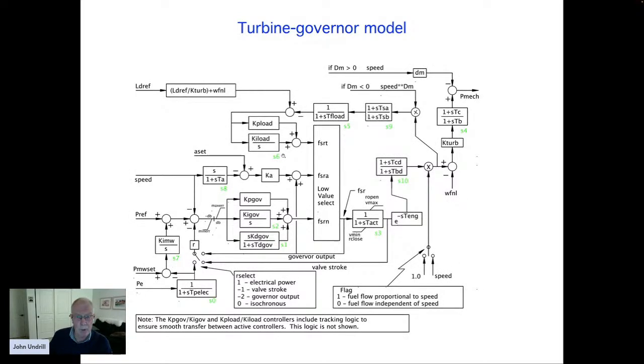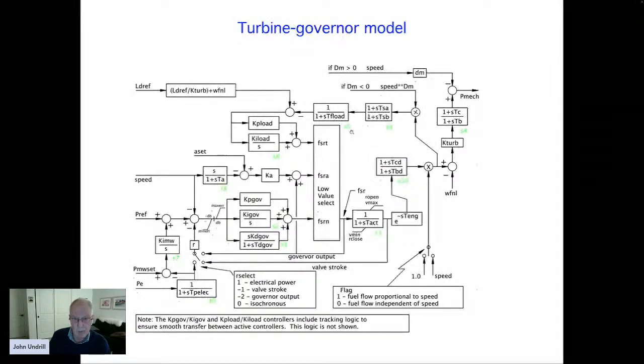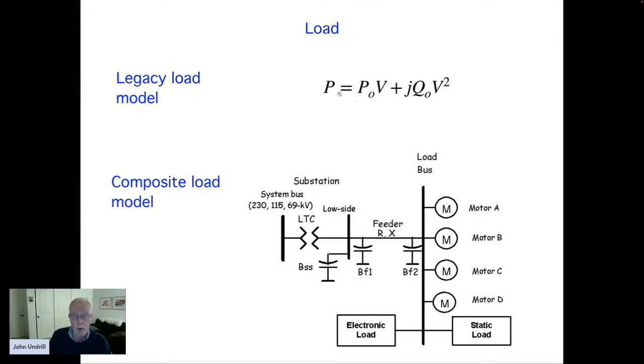Here's a more complicated one. This is what we use to represent a large single shaft gas turbine, perhaps a 250 megawatt frame 9 gas turbine somewhere in the 50 cycle world, a little bit smaller machines for 60 cycle world. The governor is a proportional and integral controller. There are temperature limits which are implemented by a proportional and integral gain, and a whole lot of interaction between various signals. The loads are also no longer to be treated as constants.